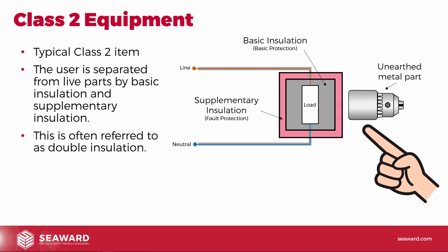So in this case, by having the 2 layers of insulation built in, we're not reliant on the resistance of that earth path. We're also not reliant on the safety of the earth in the fixed installation. So sometimes you might be doing work in properties where you think, actually, has this installation ever been tested? How do I know the earth in the installation's okay? My appliance might be fine, but do I know the installation's safe? Whereas with double insulated equipment, the fault protection is built into the equipment. So it's safer. Normally class 2 equipment tends to be equipment that's got more of a plasticky construction.